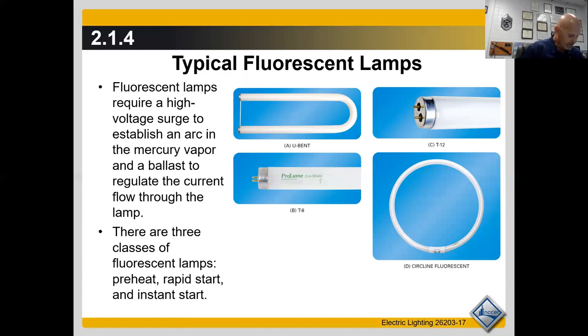Fluorescent lamps have two electrical requirements. A high voltage surge is needed to establish the arc in mercury vapor. Once started, the gas offers decreasing resistance, so current must be regulated. Otherwise the lamp would draw more and more power and rapidly burn out. This is why fluorescent lamps operate in fixture circuits containing a ballast that provides the required voltage surge to start up and then controls current flow.